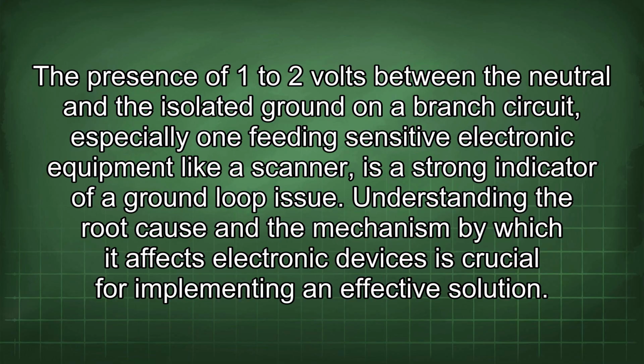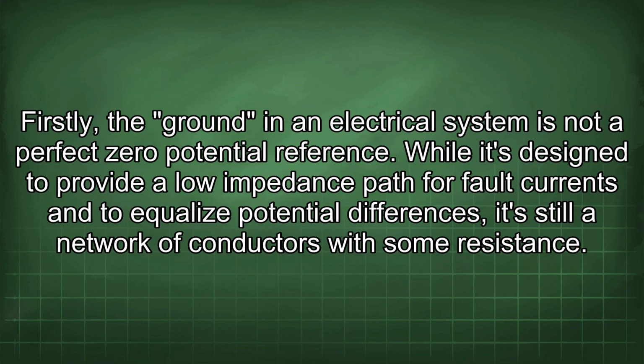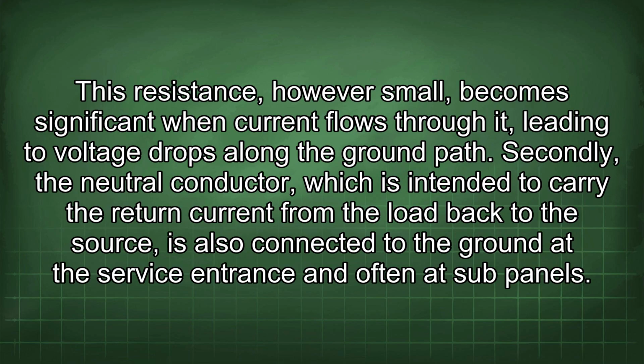Understanding the root cause and the mechanism by which it affects electronic devices is crucial for implementing an effective solution. Firstly, the ground in an electrical system is not a perfect zero potential reference. While it's designed to provide a low impedance path for fault currents and to equalize potential differences, it's still a network of conductors with some resistance. This resistance, however small, becomes significant when current flows through it, leading to voltage drops along the ground path.